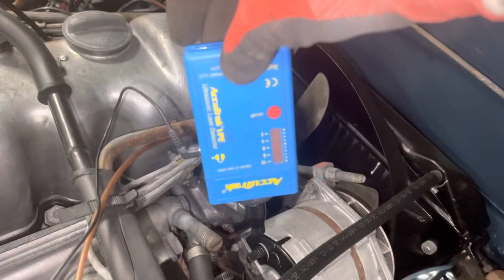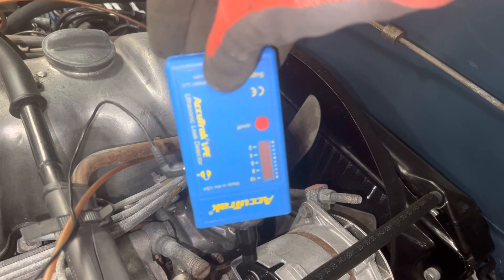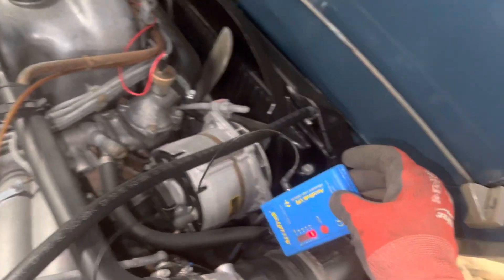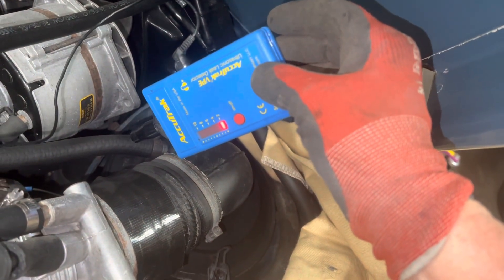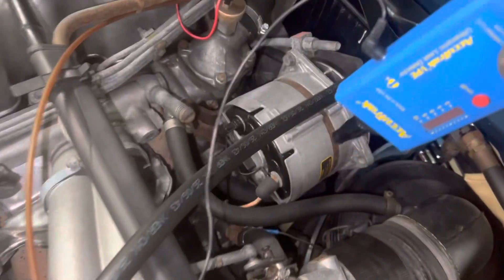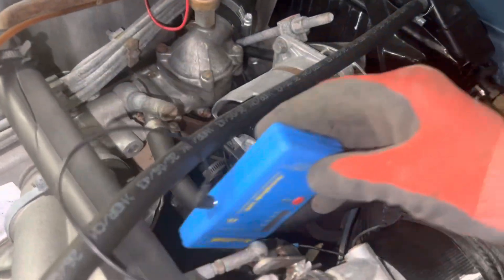You see that light? In my ears I'm starting to hear the leak from this distance - I'm way up here. It's even louder right there. From this distance I can tell there's a leak somewhere down in that general vicinity. There's not much room down here, so I'll get a little closer - you can see the signal gets a little higher.